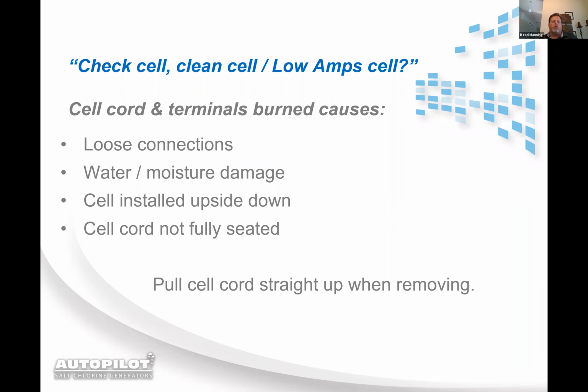The post that the cell cord plugs down onto on the cell, they're titanium. They're impervious to that corrosion. But what happens is once you get corrosion on the copper brass, then you've got a gap between the copper brass connection inside the cell cord and the titanium post on the cell, and it will start arcing on that cell plug, and it will actually pit the titanium. The cell cords actually come with a black substance that's around the copper brass connections. That stuff has a low heat threshold. So if your cord does start arcing against the post, it should melt that black stuff. So if you ever get to a job and see some black oozy stuff coming out of the cell cord, it means that cell cord is arcing, it's overheating, you need to replace it.